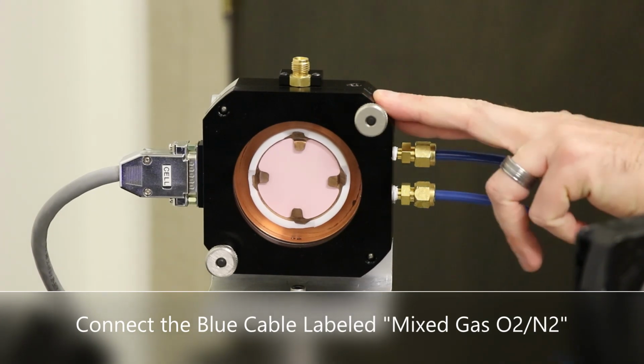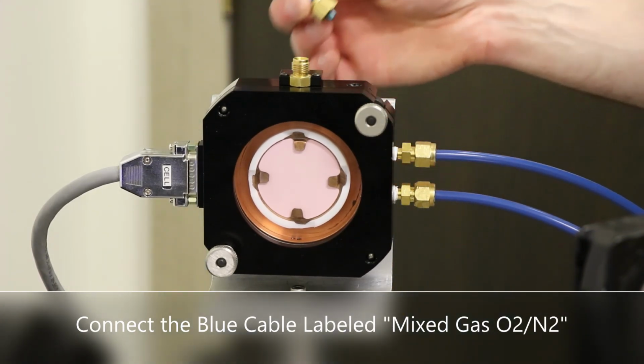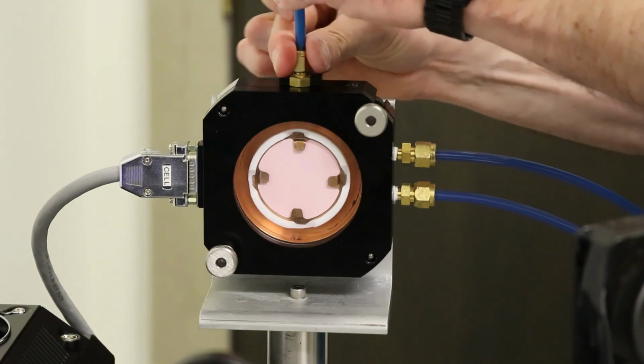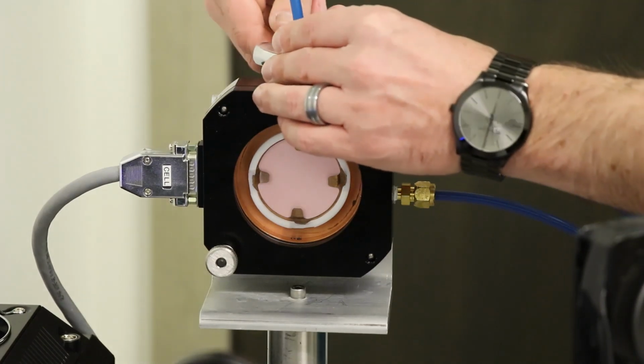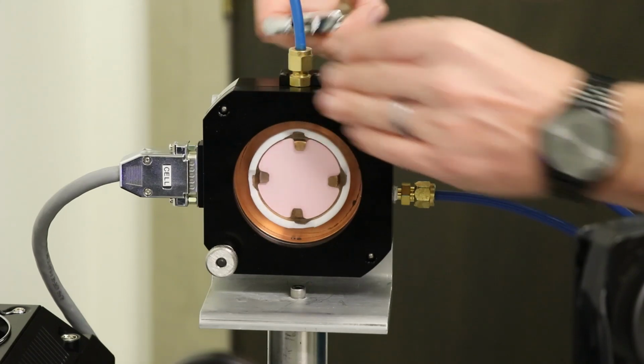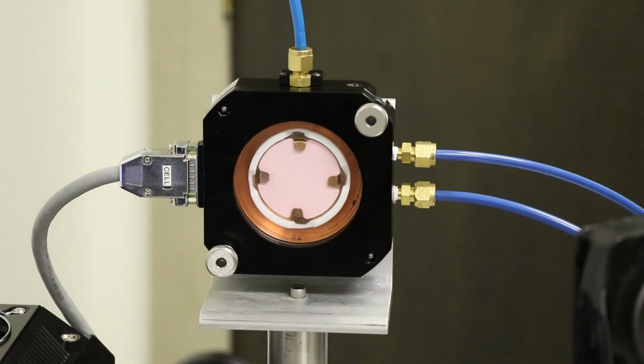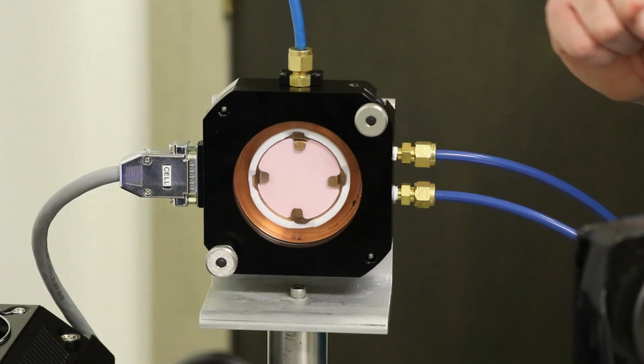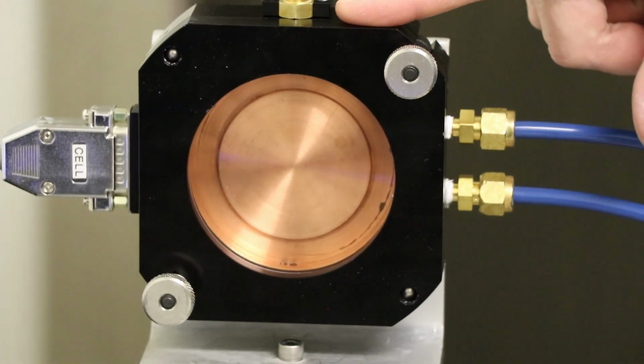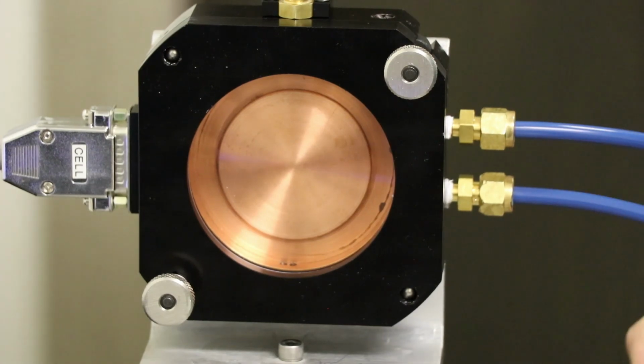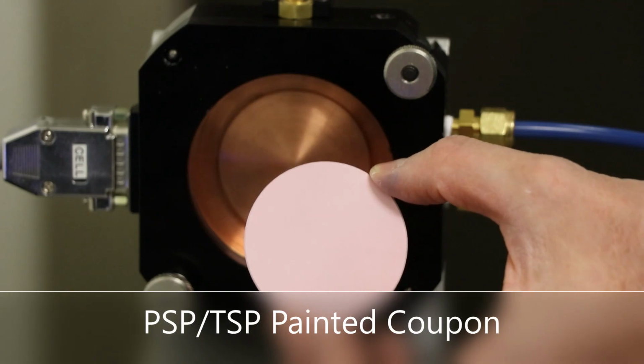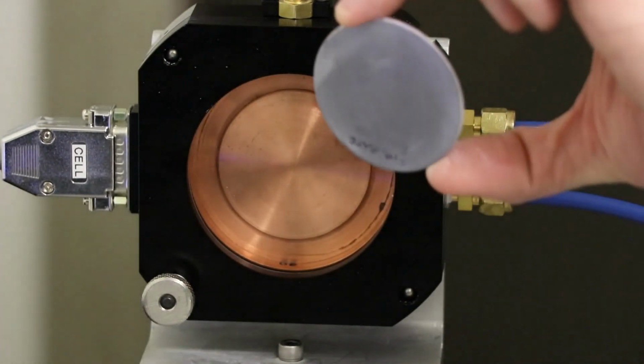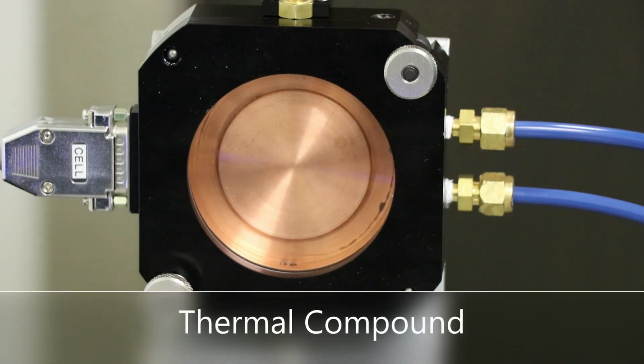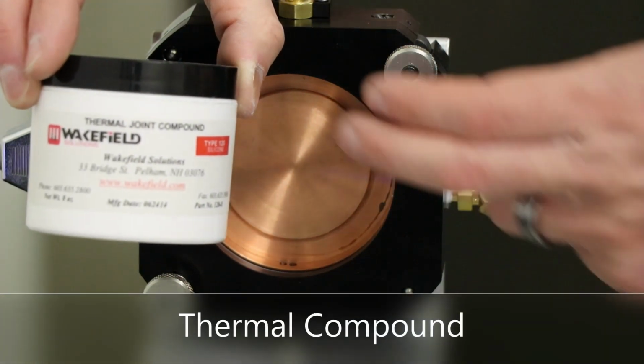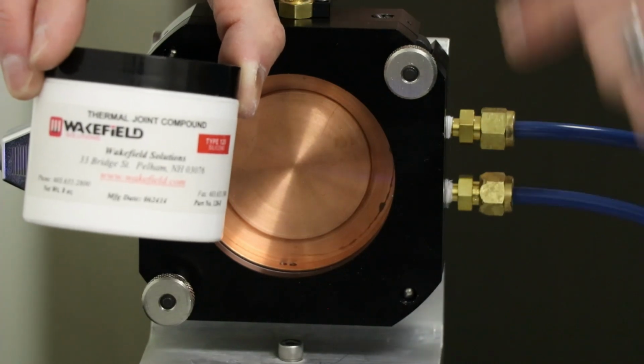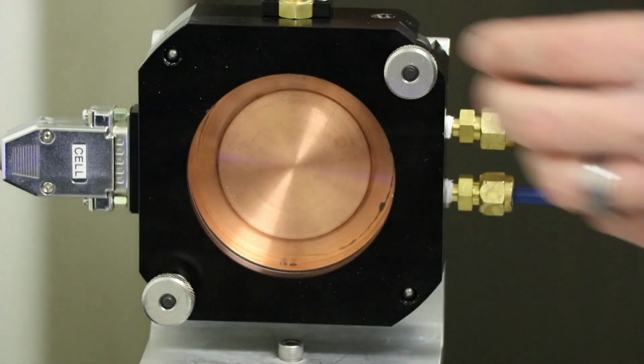The last connection we need to make on the cell itself is the gas supply coming into the cell. Just get this tight with your hand and then very lightly with the wrench, and that's good. This will make an airtight connection for the incoming gas flow. So next we need to install the actual sample into the calibration cell. So we have a sample painted with PSP here. One side painted, one side unpainted. And we have a thermal compound here, which we will use to make good thermal contact between the sample and the copper heatsink of the cell itself.